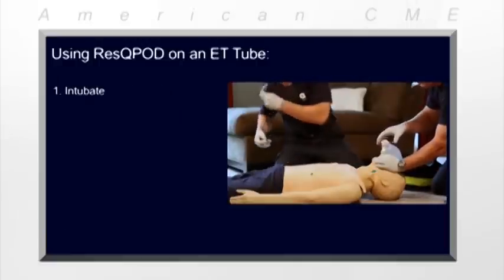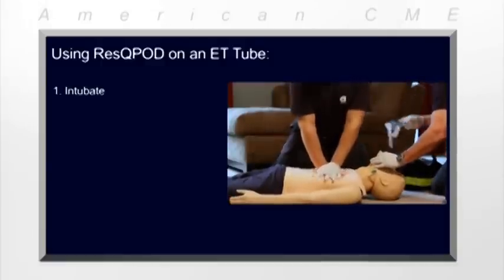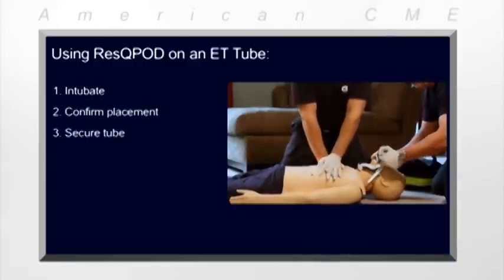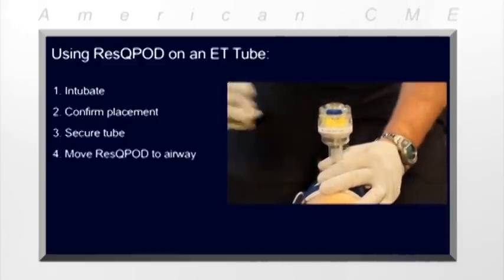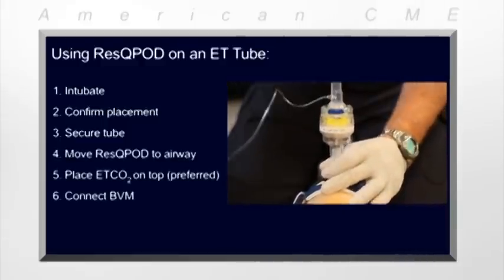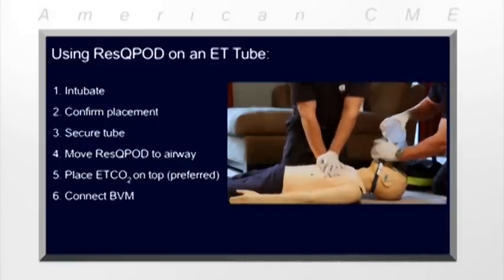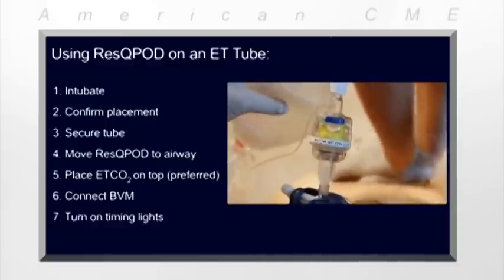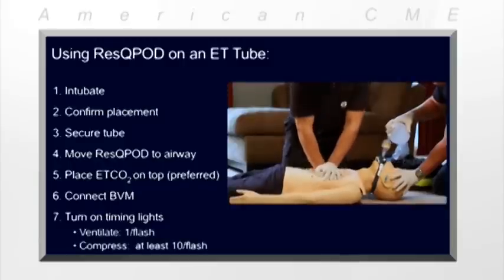The ResQPOD can also be used on an advanced airway such as an endotracheal tube or supraglottic airway. Once tube placement is confirmed, secure the airway with a commercial tube holder. Then move the ResQPOD to the airway. Connect the end-tidal CO2 detector and the ventilation bag to the top of the ResQPOD. Next, turn on the timing lights — they flash ten times a minute and can be used to guide both chest compressions and ventilations. Provide one ventilation and at least ten compressions with each light flash.